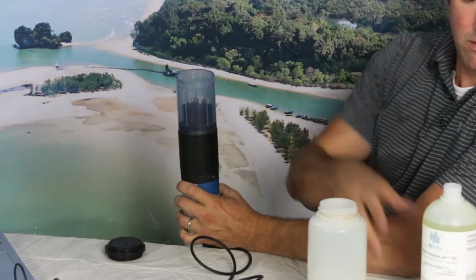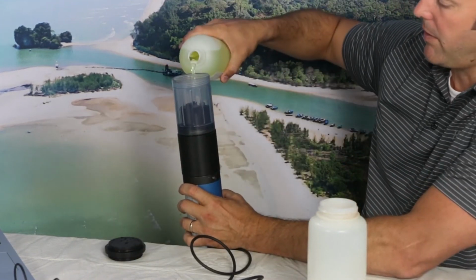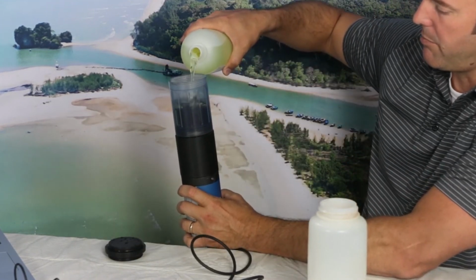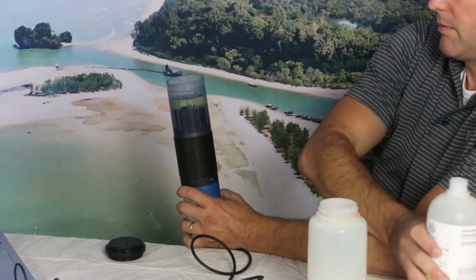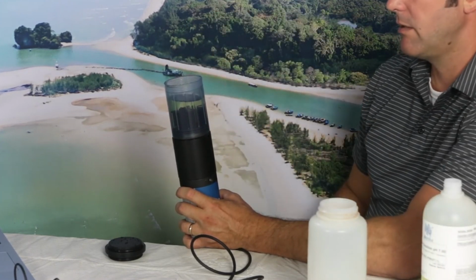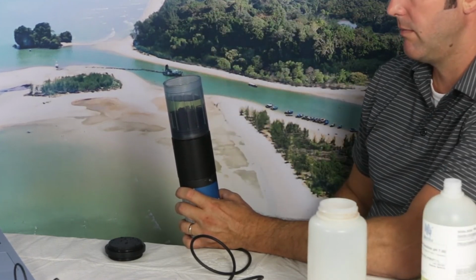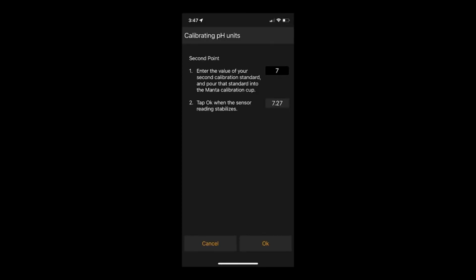Then finally, fill the cup up to where all of your sensors are submerged. Wait for the reading to stabilize, and then click OK. You will then be prompted to calibrate your second point. With your second calibration solution in the cup, type the value of the solution, wait for the reading to stabilize, and then tap OK.